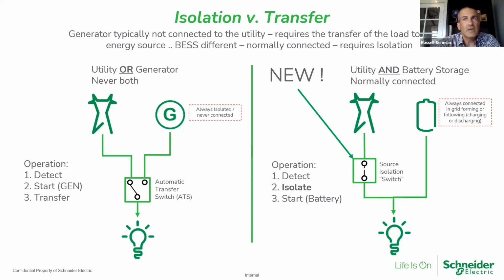So walking through how the battery energy storage system would work: normally I'm connected, I might even be net metering. If I'm connected with solar and the sun is high and I'm creating more energy than I need, I may be selling power back to the utility. But then a lightning storm takes out a power pole and the power goes out. I'm still connected, but now I want to disconnect because I want to create energy for my building so I can turn it back on. That's when you need that switch to open.